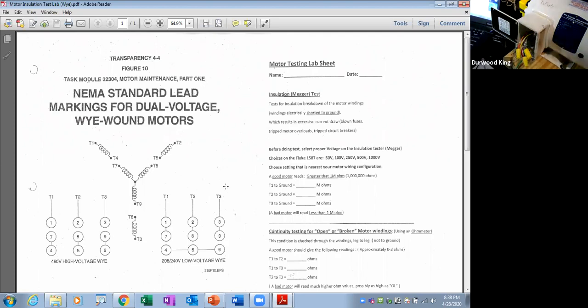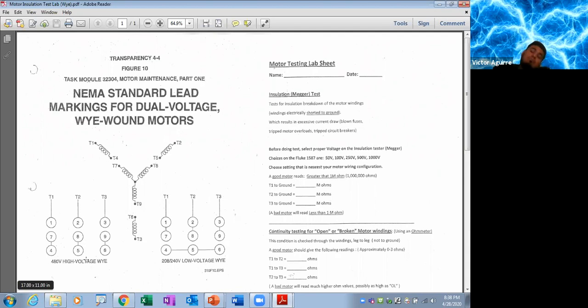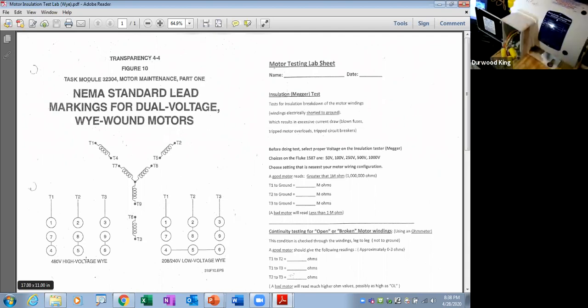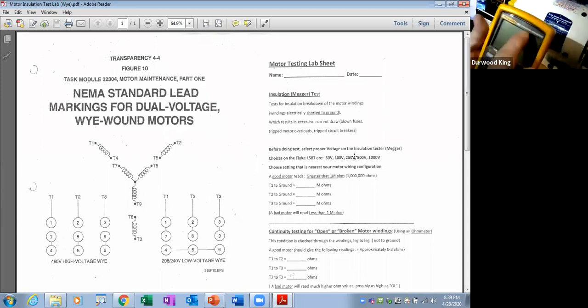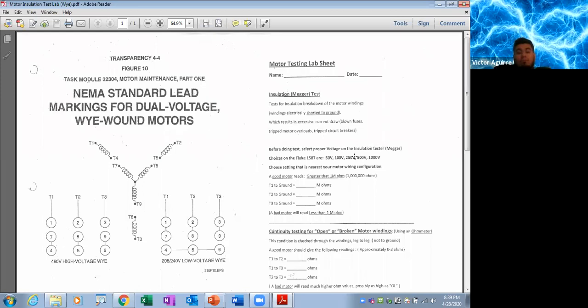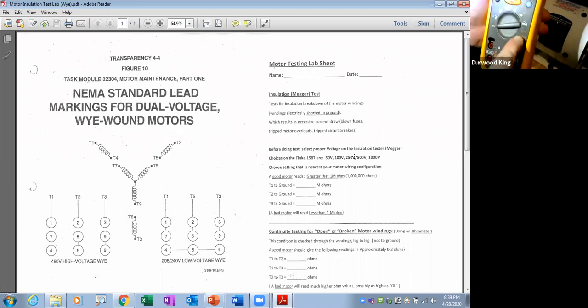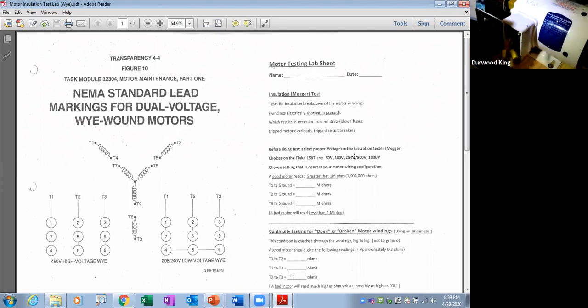Now, when you test a motor, here's what you want to do. You want to wire the motor on the high voltage side so you get the best test out of it at the highest voltage on the test meter, because the test meter is actually going to produce high voltage and inject voltage into the motor and test it under voltage. Okay, so let's take a look at how you do that. Now, first of all, if you look at the lab test over here, it's telling you to put the voltage range that the meg tester or insulation tester, the meter is actually called an insulation tester. You see that right there where it says insulation multimeter? Yes. Yeah. It's an insulation tester. It actually does multimeter functions like regular, plus it has an insulation test over here that actually generates voltage in here, and it shoots voltage into the motor and finds any leakage that may be in there.